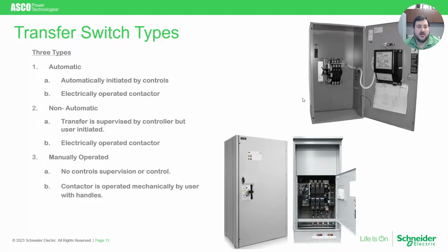And this is important for applications where a high degree of human supervision and control is required before the system automatically takes any actions. And lastly is a manually operated switch. A manually operated switch has no controls or supervision to the controls, and the contactor is physically operated by the user by turning a handle.